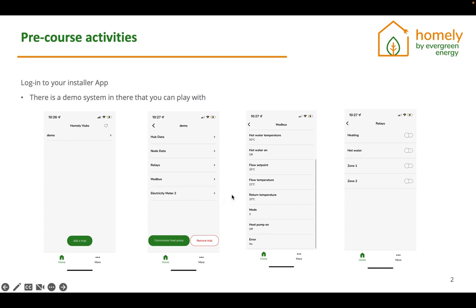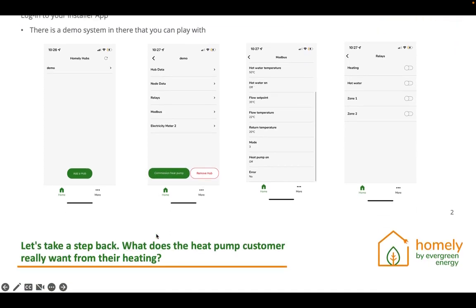And the last section here is the electricity meters. We don't, at the moment, ask people to install electricity meters, but Homely can actually read an electricity meter that has a Modbus connection. So in there, you could daisy chain the Modbus connection into the heat pump and the electricity meter, and then you could see the information that the customer would be able to see on that electricity meter. Also here, you'll see a commission heat pump button, which I'll talk about a little bit later on.